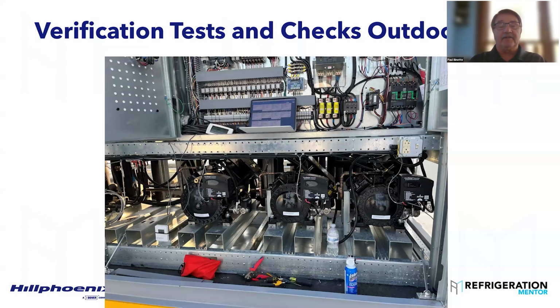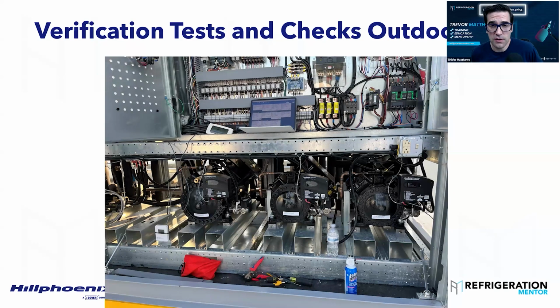You want to make sure that the joints that have been brazed in place are going to hold. And that's different in your jurisdiction, because here in Canada, you have to do 10% above the pressure relief. So if you have a 1900 psi pressure relief, for example, you have to pressure test over 2000 psi. So make sure, depending on where you're doing this, because there's people listening from around the world, follow your local codes.